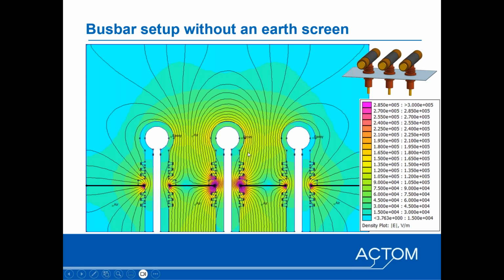So with a potential difference, and pollution on the surface of the insulation, you will then have leakage current flowing over the insulation surface. You've also got high field concentration at the interface where the bushing goes through the metal sheet, which, if you're not having a proper insulation material, or the bushing is not properly dimensioned in terms of the dielectric strength, would then cause a breakdown in that zone.